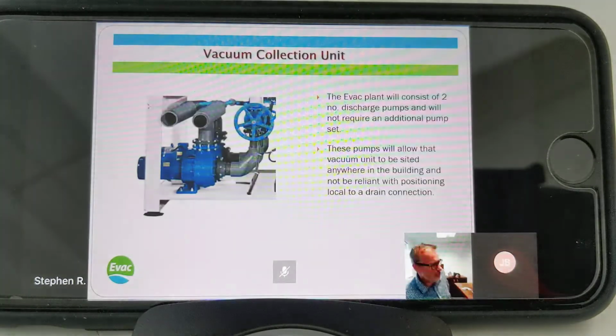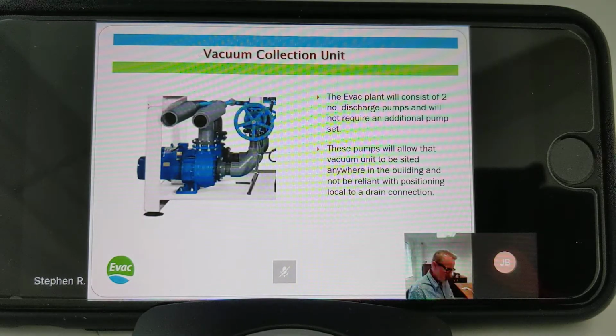Then we have our discharge pumps. The discharge pumps will kick in and empty the tank when the level switch is reached inside. They don't drain the tank right down to the bottom. The reason for that is it keeps those pumps primed. And secondly, all of those foreign objects that I've mentioned do go down a vacuum system, because believe it or not, people do treat this as a waste disposal system. If we don't empty the tank completely, they stay in the tank, they don't get poured into the pump, and they're then removed during the maintenance times.